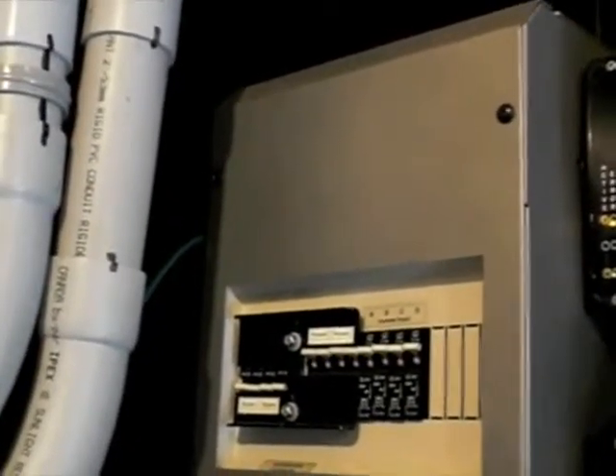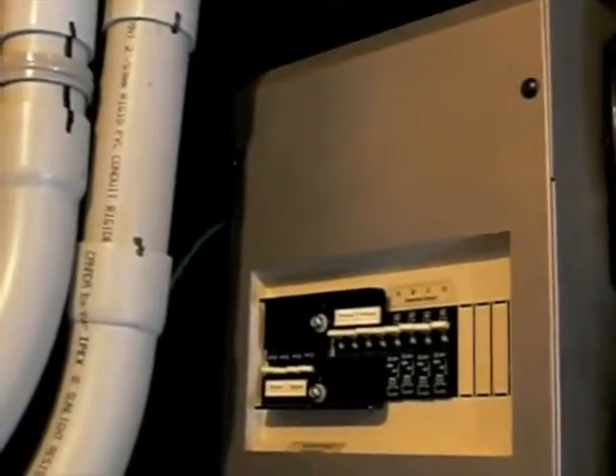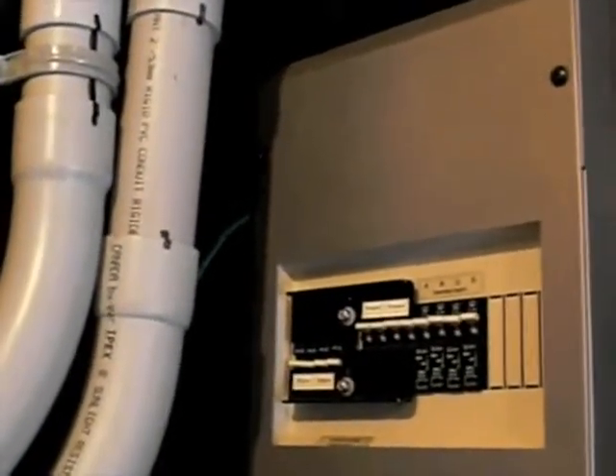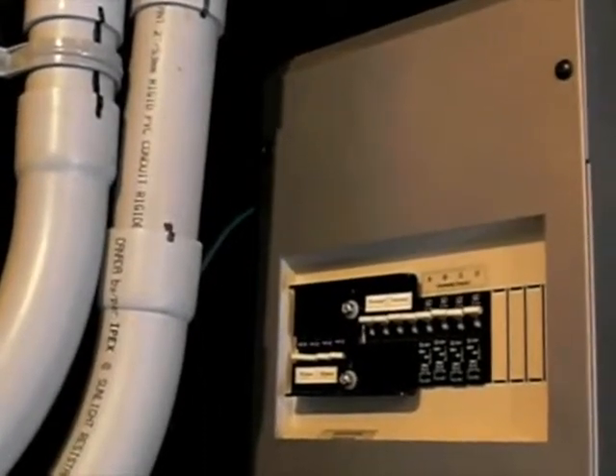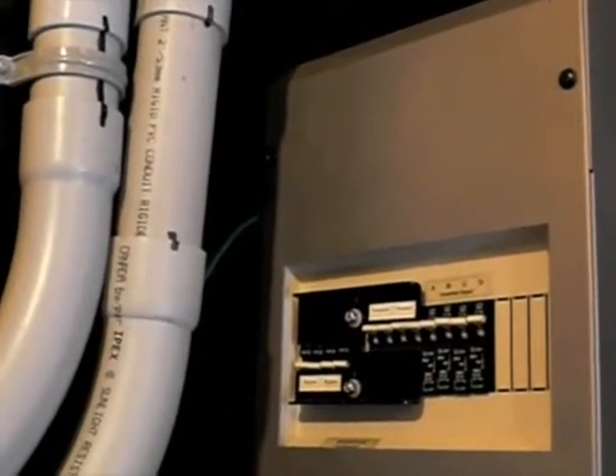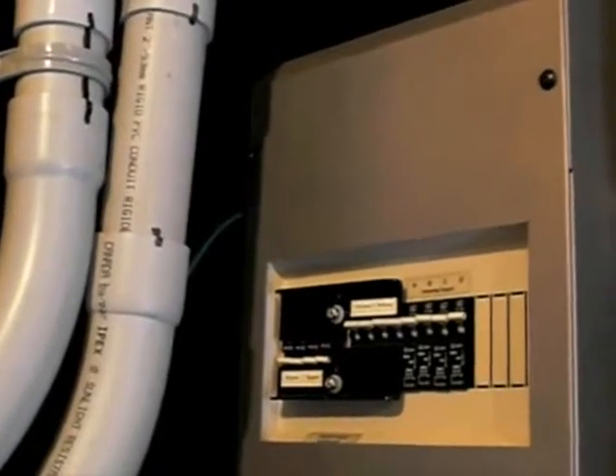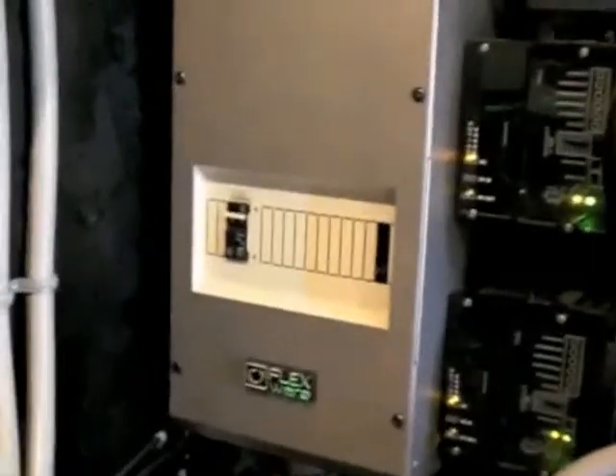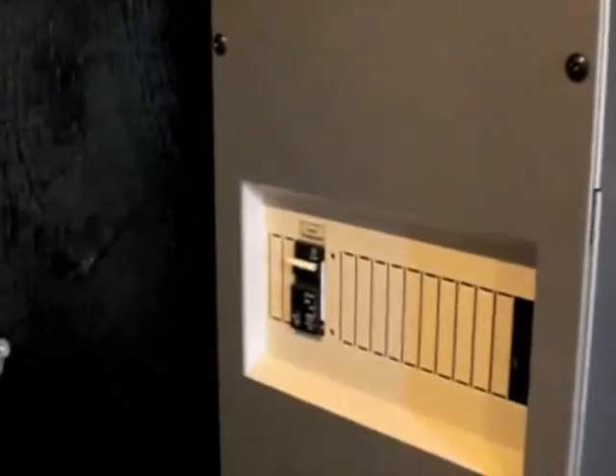And also on the left, on the interlock here, we have a bypass circuit as well, so we can run a generator with this system and just bypass the inverters altogether, or we can actually take charge from the 18 kilowatt diesel generator that's 800 feet away and charge the batteries. And on the lower set of breakers there is just one double breaker for the auto transformer, which is inside of this unit.